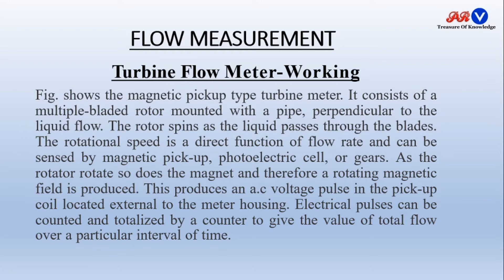As the rotor rotates, so does the magnet, and therefore a rotating magnetic field is produced. This rotating magnetic field produces AC voltage in the pickup coil located external to the meter housing. Electrical pulses can be counted and totalized by a counter to give the value of the total flow. These pulses can be counted, and the sum of the counter gives the total flow over a particular interval of time. So in this way we get the flow reading from the turbine flow meter.